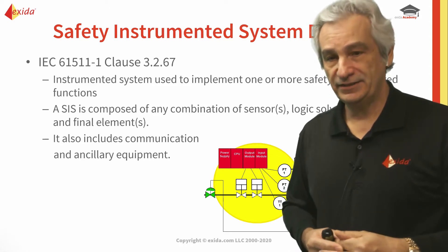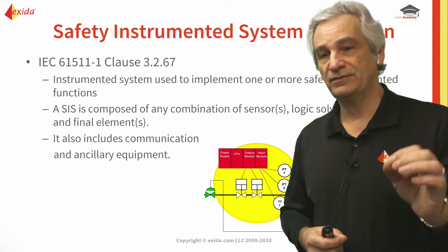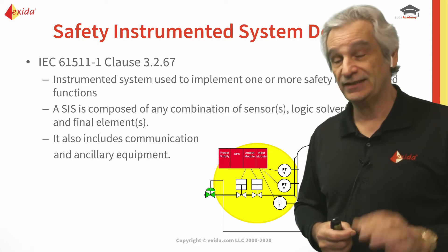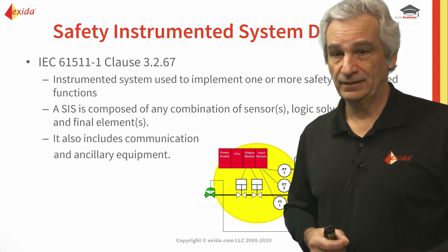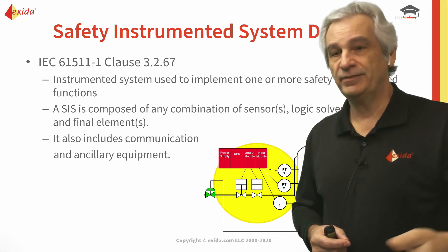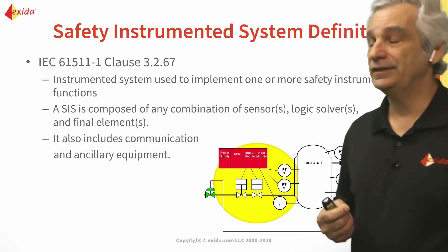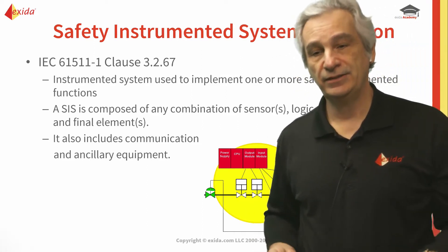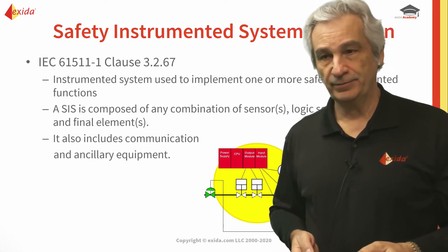The reason is that a safety instrumented system can consist of one or more safety instrumented functions, and these safety instrumented functions can have different SIL requirements. That is the important distinction. A SIS is composed of combinations of sensors, logic solvers, and final elements, and it can include ancillary equipment such as power supplies and communications — all of which must be considered, certainly from the logic solver point of view.